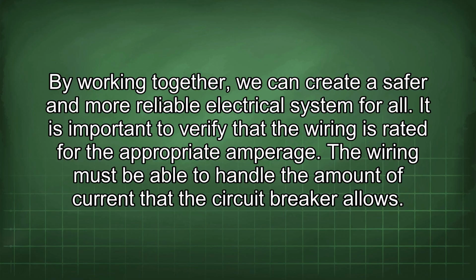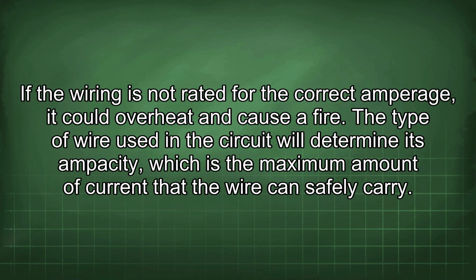It is important to verify that the wiring is rated for the appropriate amperage. The wiring must be able to handle the amount of current that the circuit breaker allows. If the wiring is not rated for the correct amperage, it could overheat and cause a fire. The type of wire used in the circuit will determine its ampacity, which is the maximum amount of current that the wire can safely carry.